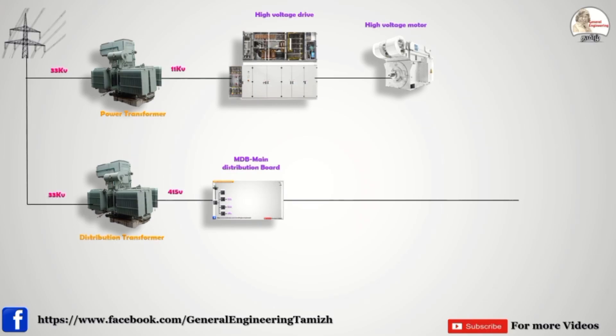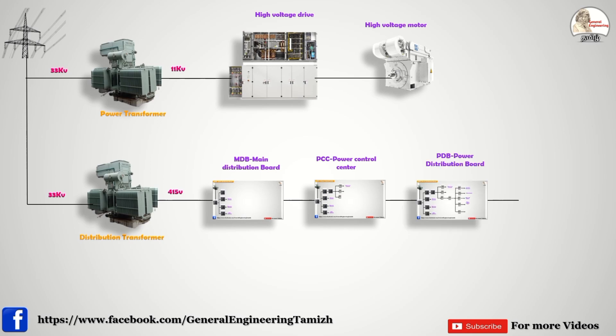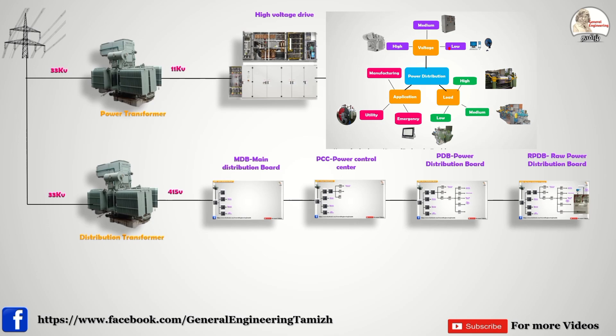From the MDB panel we connect two panels: the Power Control Center (PCC) and the Power Distribution Board (PDB), where medium kilowatt equipments are connected. From PDB we connect the RPDB — the Raw Power Distribution Board — where all single-phase equipments are connected. So voltage-related and kilowatt-related distribution is now complete.